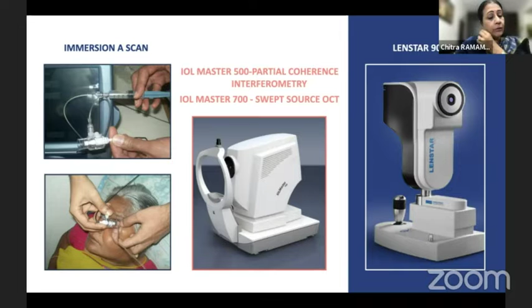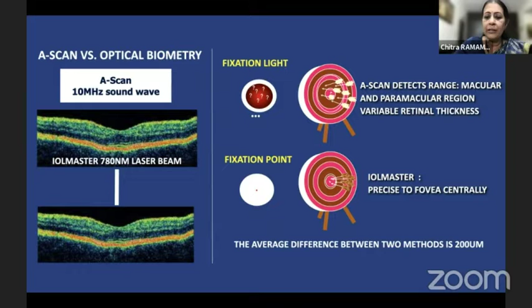And then pearl number 3 is the precise biometry. I do know, all of us know, that the immersion biometers are doing good. So are the different optical biometries, which have come in based on different principles. Essentially, there are small changes which happen with the optical biometer, is that the frequency of the laser beam is very significantly high, and it's able to identify the exact fixation point precisely on the fovea, and the actual difference between an immersion and the optical biometer is just about 200 micron. But having said that, there are many of us using immersion biometry. So what attention to detail is needed is, you should check whether all those spikes on the cornea, the lens, the retina, everything should be of nearly equal amplitude, and you keep your gain at the lowest level at which you're getting these equal spikes.